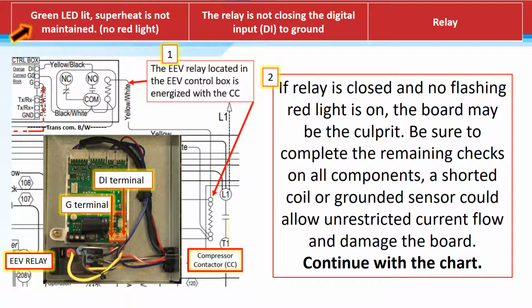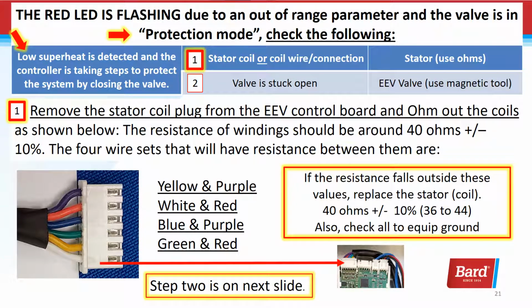We need to complete the remaining checks in the manual on all components. A shorted coil or a grounded sensor could allow unrestricted current flow and damage the board. Here, the red light is flashing due to an out-of-range parameter and the valve is in protection mode. We need to check the following. The valve is seeing low superheat and the controller is taking steps to protect the system by closing the valve. Number 1, the stator coil or coil wire connection.